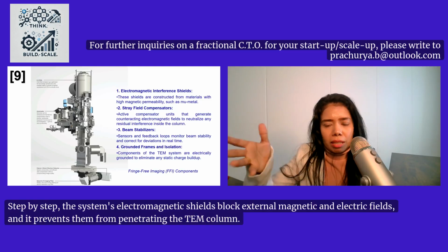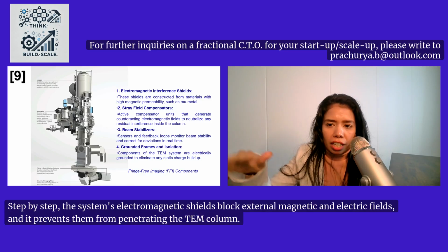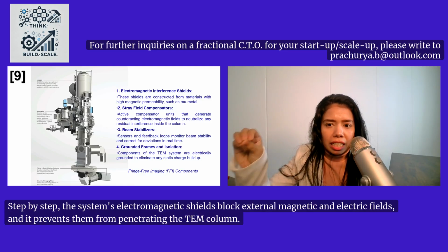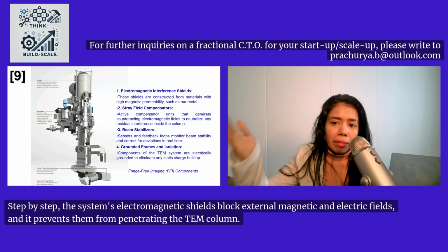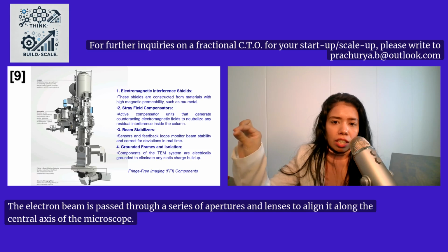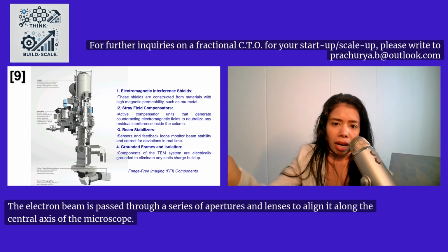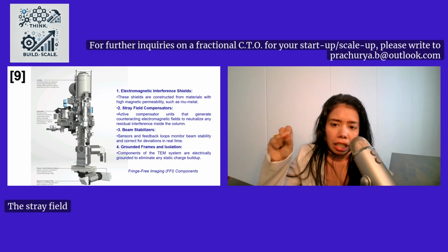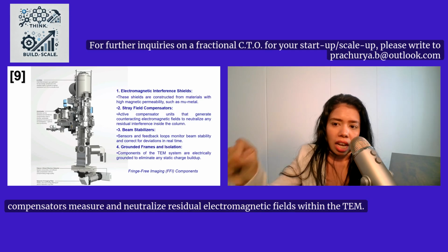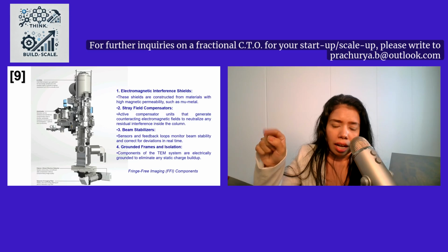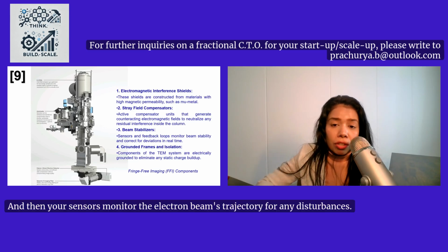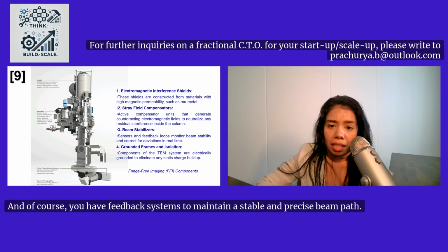Step by step, the system's electromagnetic shields block external magnetic and electric fields and prevent them from penetrating the TEM column. The electron beam is passed through a series of apertures and lenses to align it along the central axis of the microscope. The stray field compensators measure and neutralize residual electromagnetic fields within the TEM. Then your sensors monitor the electron beam's trajectory for any disturbances. And of course, you have feedback systems to maintain a stable and precise beam path.